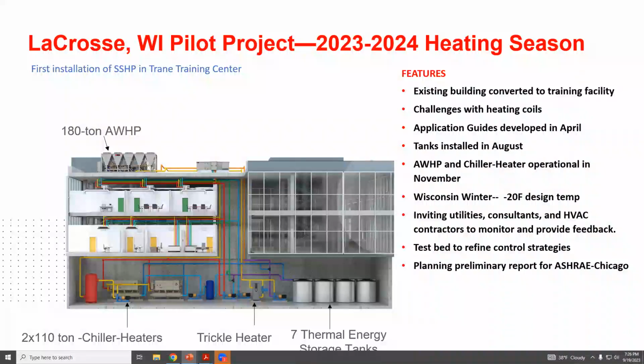This is a training center we're retrofitting with one of these water source heat pump systems. We have a 180-ton air-to-water heat pump, two 110-ton nominal chiller heaters which are screw machines, seven thermal ice tanks, and also a trickle heater, which is important.